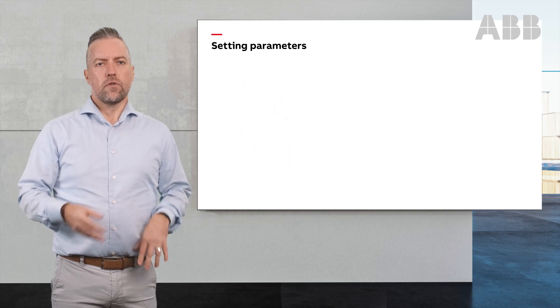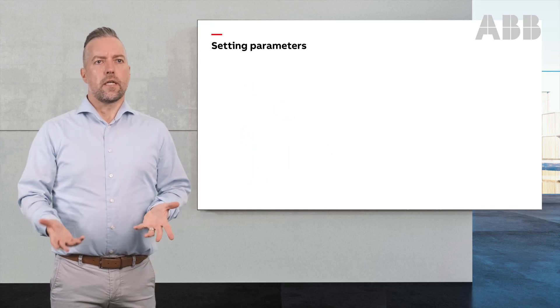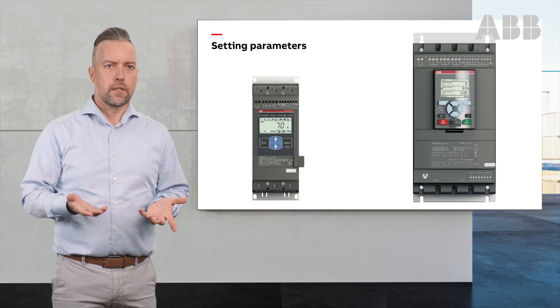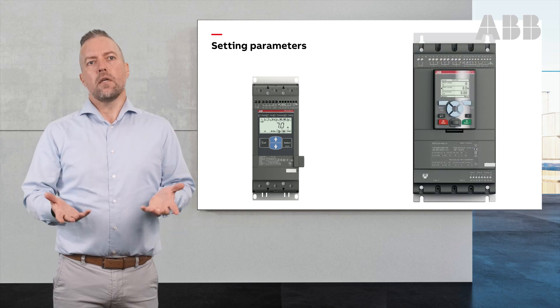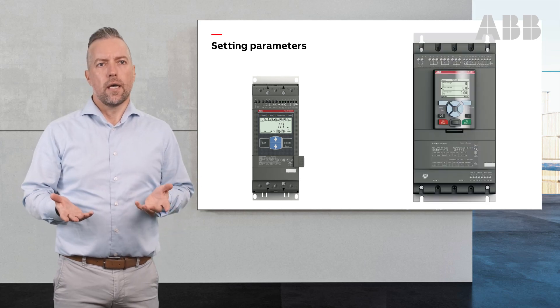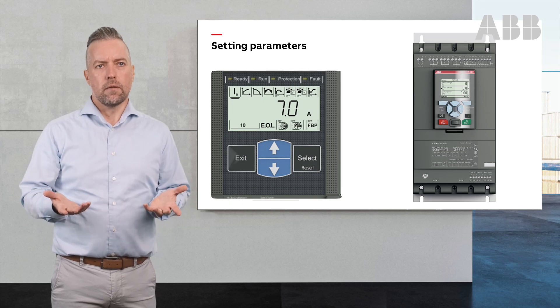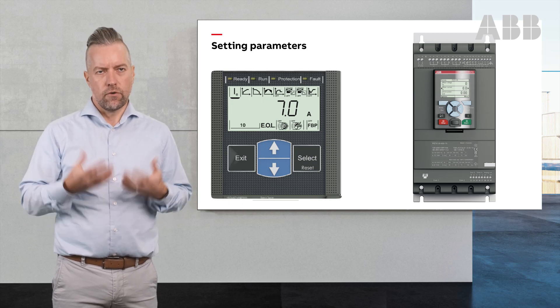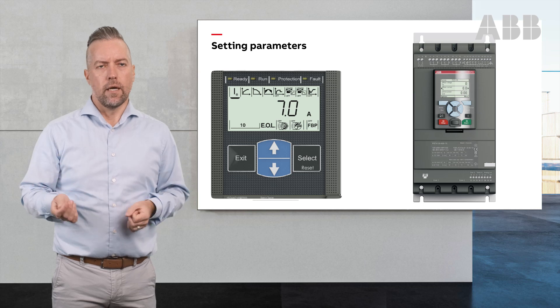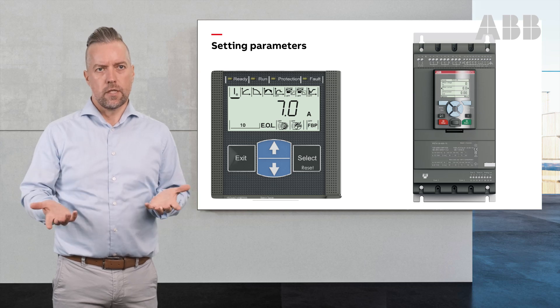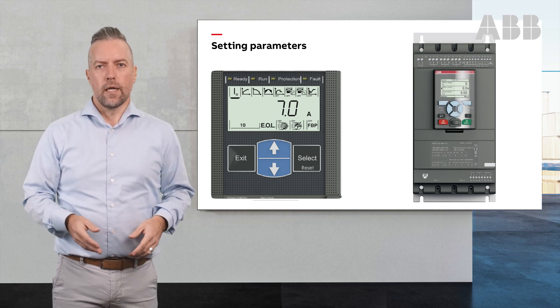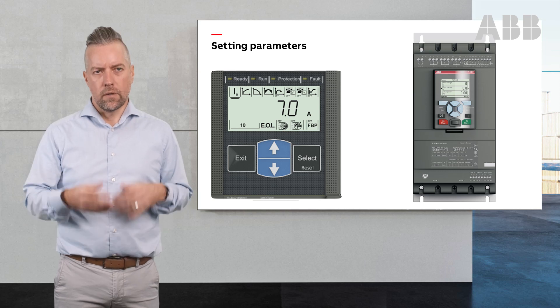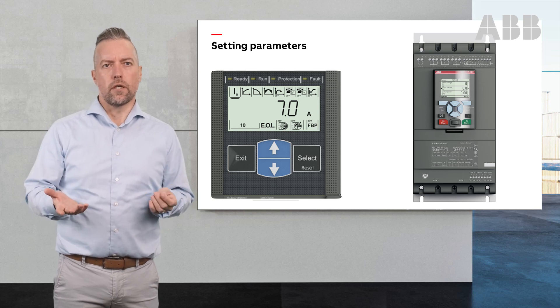You have two soft starters you can set it on: the PSE and the PSTX. If you look at the PSE, you can see it in the menu in the HMI directly on the front screen — the IE. You just push select, go in, and change that value to whatever motor rated current you have.